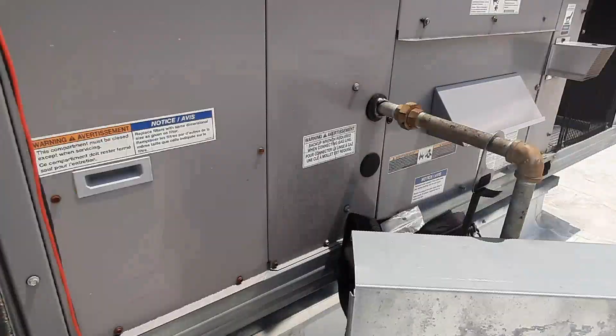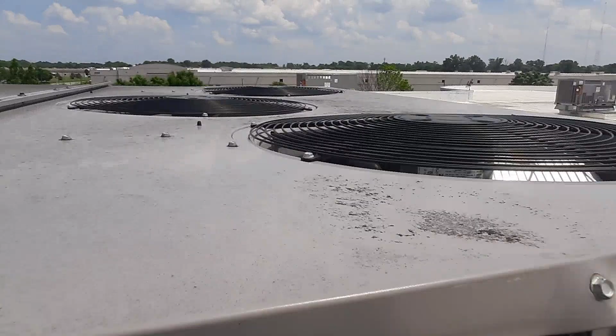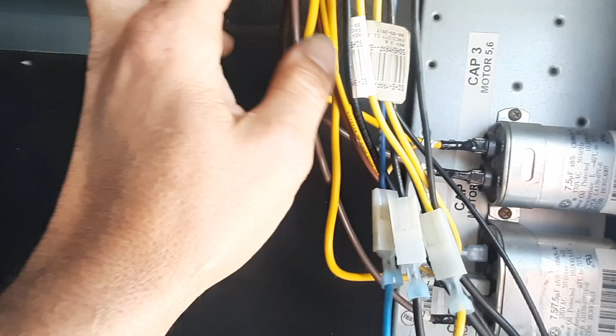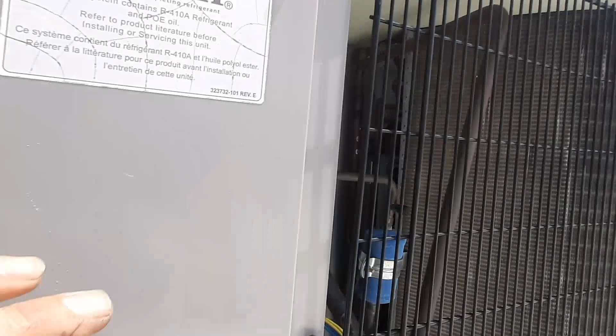So let's get over in the blower section where capacitors and outdoor fan wires sit up here and then feed over to the actual fans. We got 3 fans on this guy. So nothing looks too far off. These things are known to rub right here and anywhere along that track. You can see those wires are hanging down. Anywhere along that track or in that track, they like to rub. Capacitors don't look blown, and I don't see anything noticeable as far as shorts go.